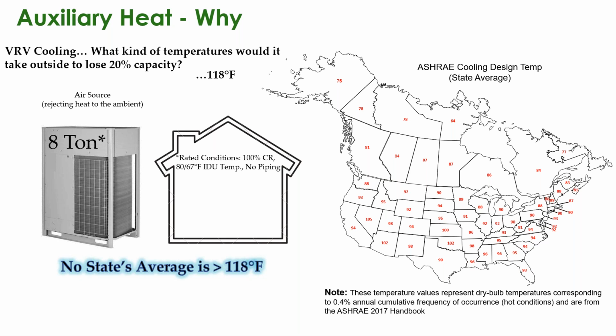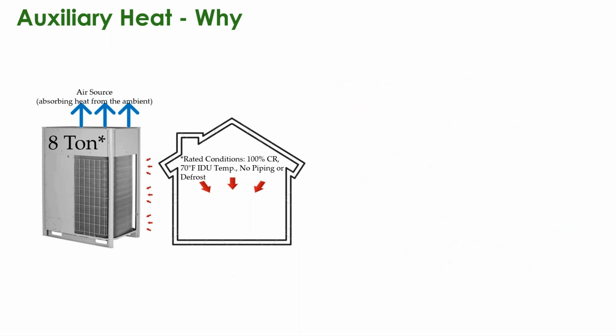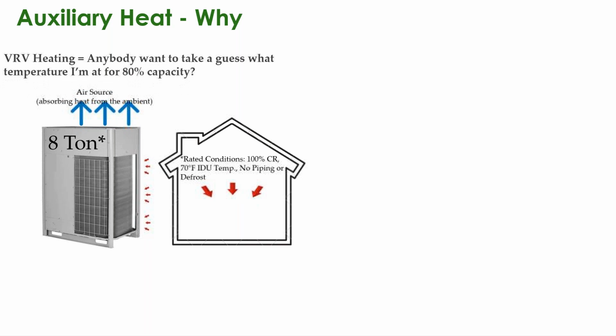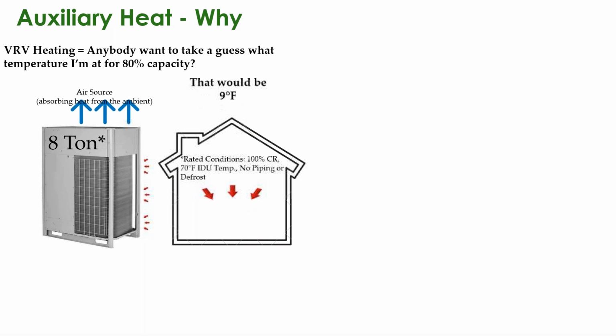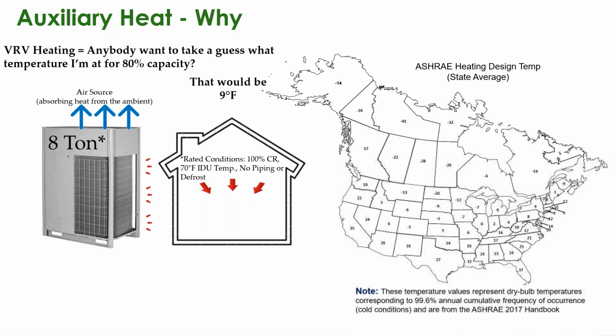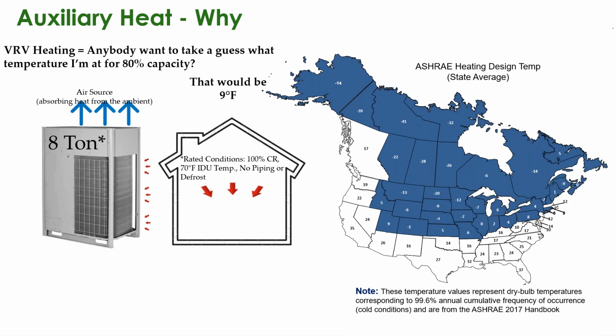When you look at ASHRAE conditions around the US, for a 20% reduction in capacity on the cooling side for your average 8-ton unit, it has to get to 118 degrees outside. Now, no state in the lower 48 or Alaska or Hawaii that I'm aware of has an average temperature of 118 degrees. So when you take that and switch it over to the heating side, anybody want to guess what it takes to lose 20% on the heat side? I'll give you the free answer. It's about 9 degrees outside on your average 8-ton that you would be at reduced 20% capacity. And you look at that across the entire US, that's a lot of areas that could benefit from a little extra heat.